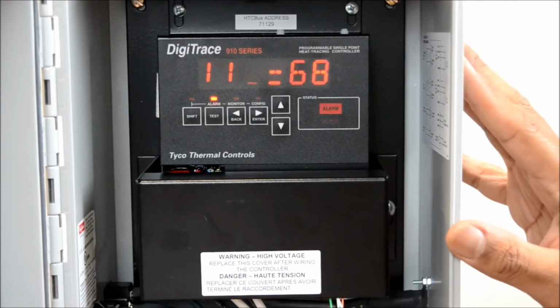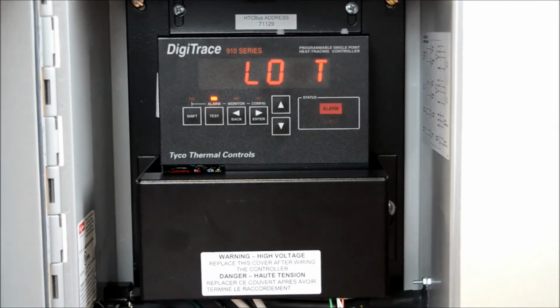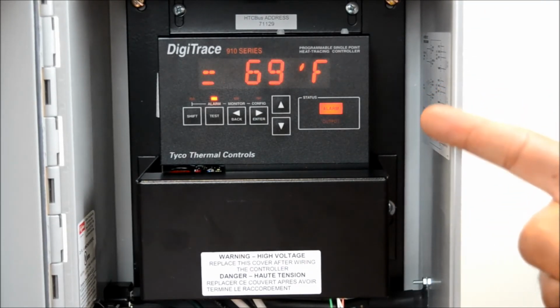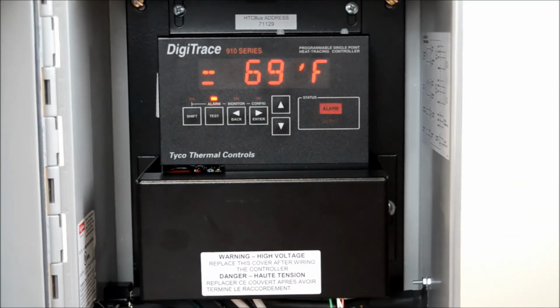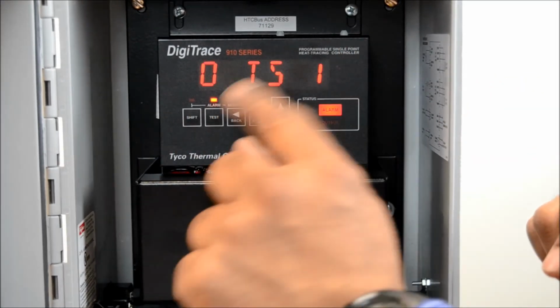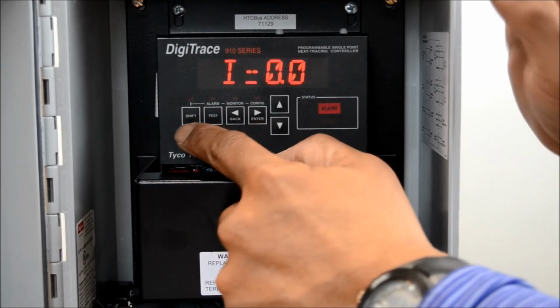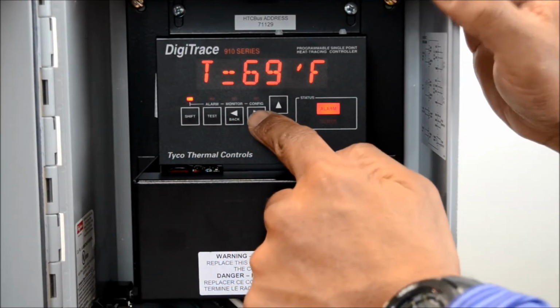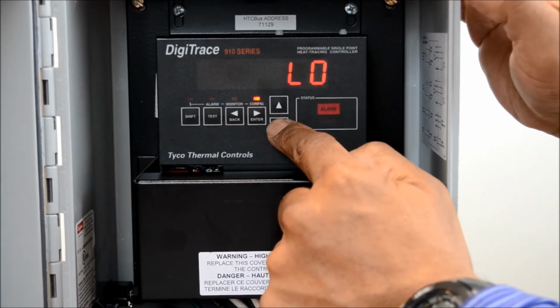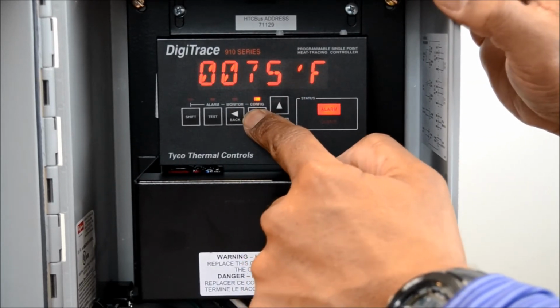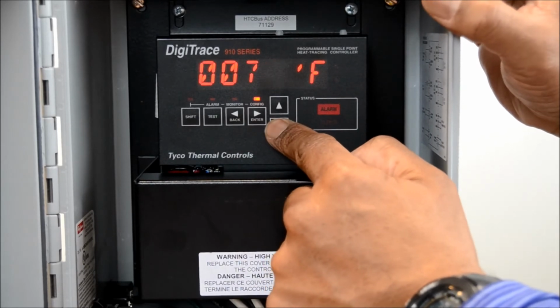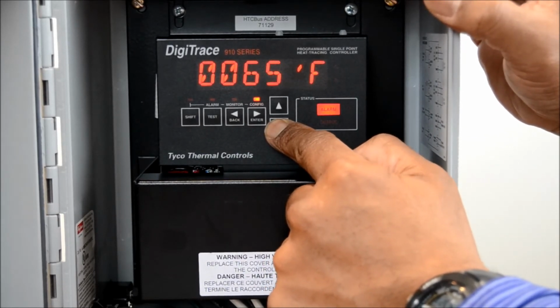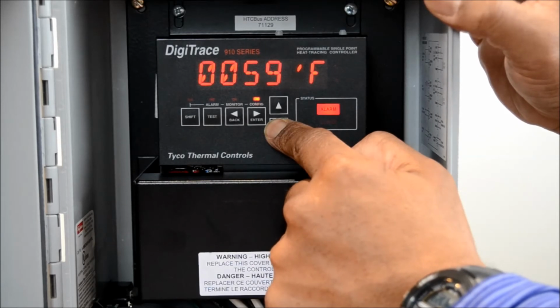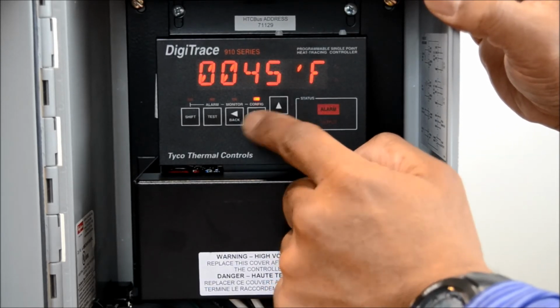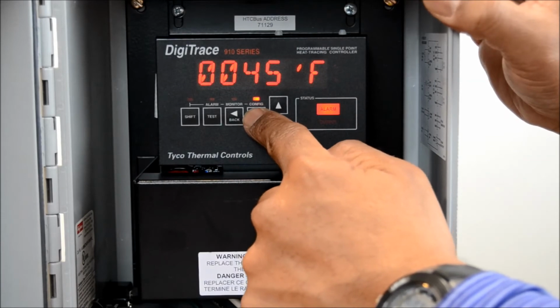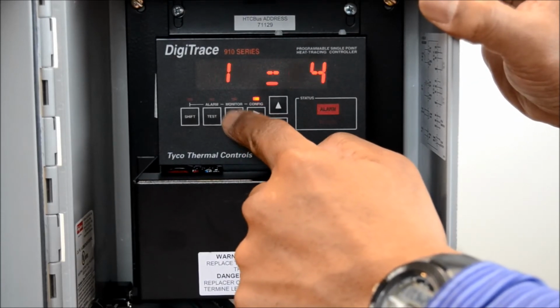If it was a ground fault alarm or this low temperature alarm, the low temperature alarm has to reach the temperature in order to get that. So what I'm going to do is clear the alarm. I'm going to go back. I'm going to hit Shift again. I'm going to hit enter. I'm going to go down to low temperature. I'm going to access that, and I'm going to go all the way down to 45 degrees. And I'm going to hit enter and then back.